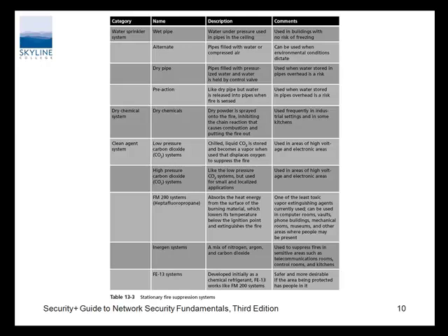I mean, there's certainly a possibility. That's why you really do have to do maintenance on these things. Do they work? Do they need to be drained? Wet systems need to be drained every once in a while and refilled with fresh water so that you don't get those sorts of things. Because water, if you let it sit, gets pretty nasty, doesn't it? All sorts of diseases and so on in it.